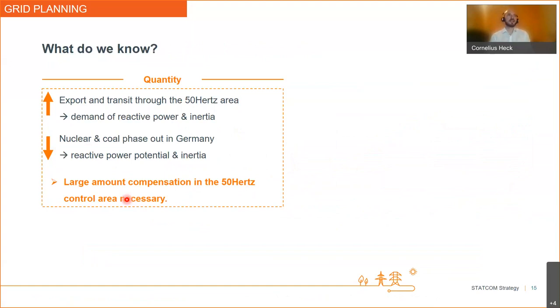So concluding the last 10 minutes, what do we know now? We know export and transit through our control area is rising, and therefore also the demand of reactive power and inertia. At the same time, nuclear and coal will phase out in Germany, leading to a lack of reactive power potential and inertia. So there is going to be a large amount of compensation that needs to be implemented in our control area.